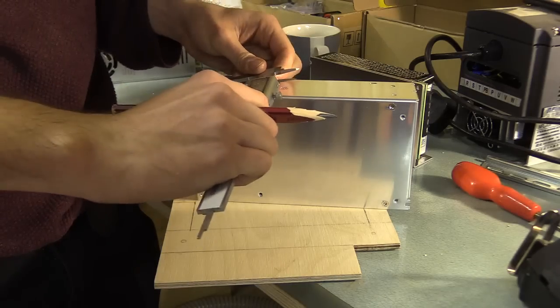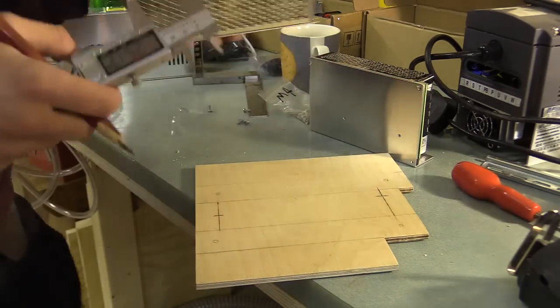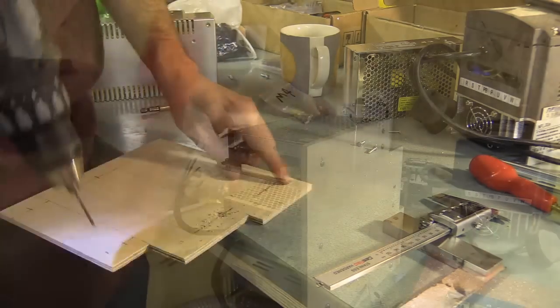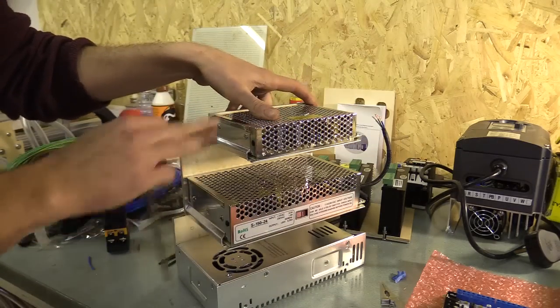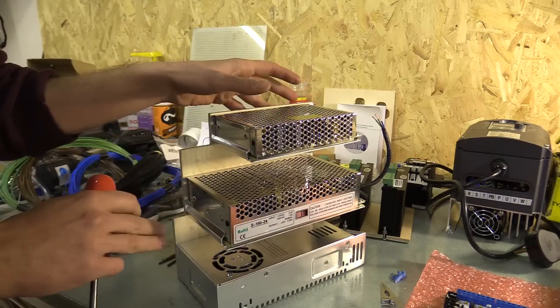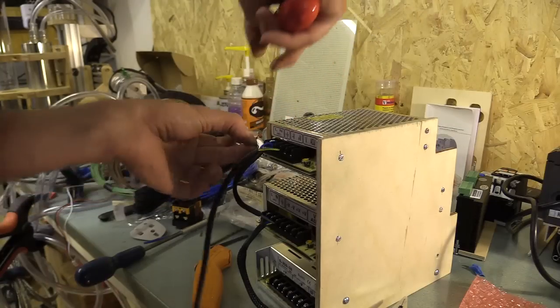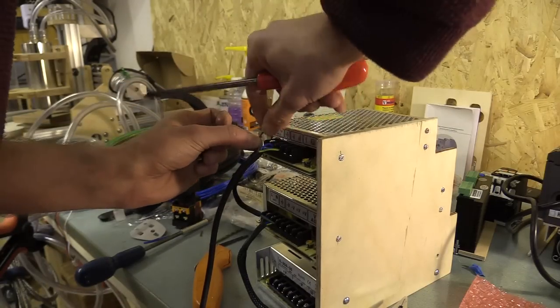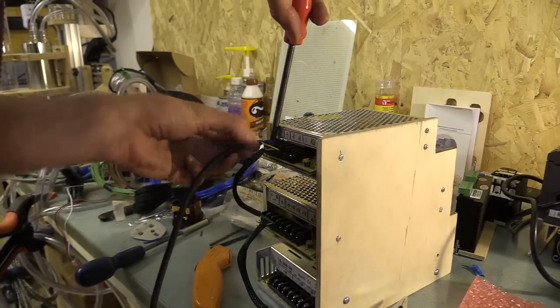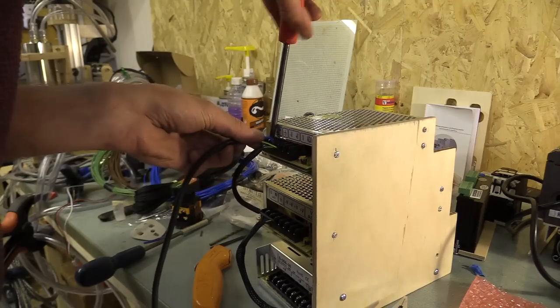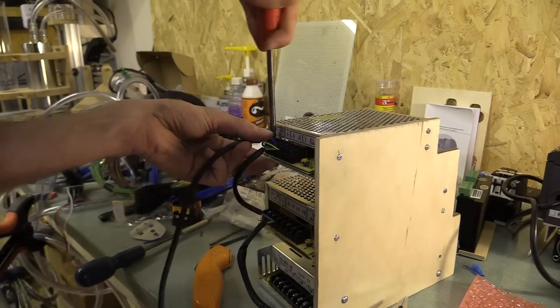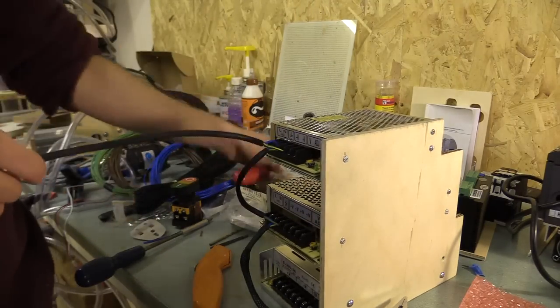Anyway I rushed to mount the power supply units and motor controllers and later when I was sleeping in bed I realized they were all wrong. I should have really installed these the other way around, would have made accessing the screw terminals a lot easier. I should have staggered the terminals of the power supply units so I could install them facing upwards. I should also reduce the space between all the components so the overall size of the enclosure is not the same size as the CNC machine I'm trying to replace.